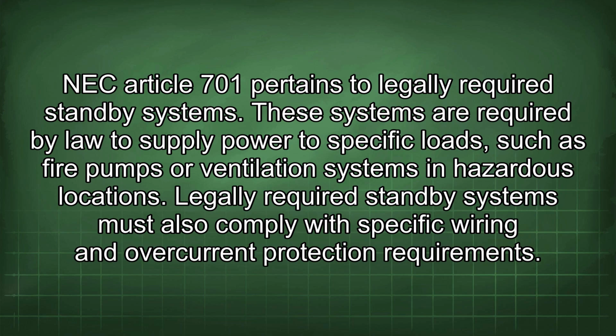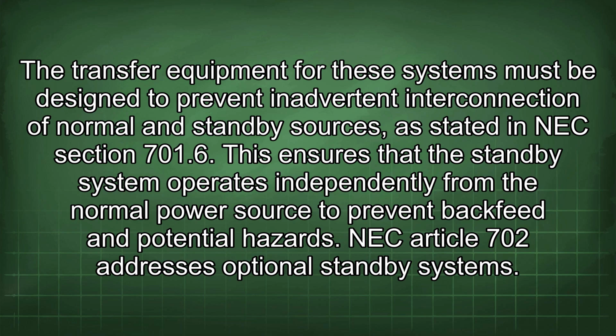Legally required standby systems must also comply with specific wiring and overcurrent protection requirements. The transfer equipment for these systems must be designed to prevent inadvertent interconnection of normal and standby sources, as stated in NEC section 701.6. This ensures that the standby system operates independently from the normal power source to prevent backfeed and potential hazards. NEC Article 702 addresses optional standby systems.